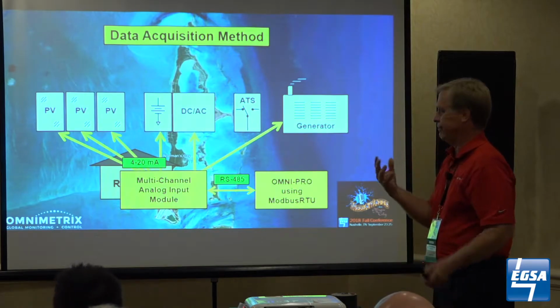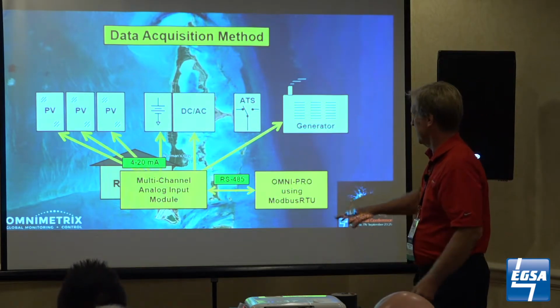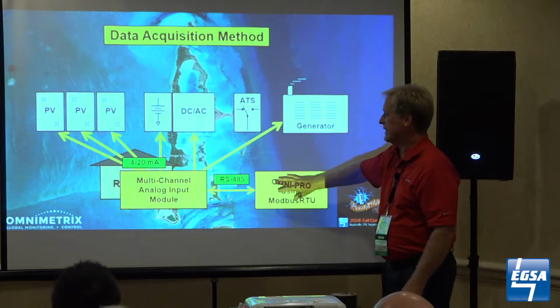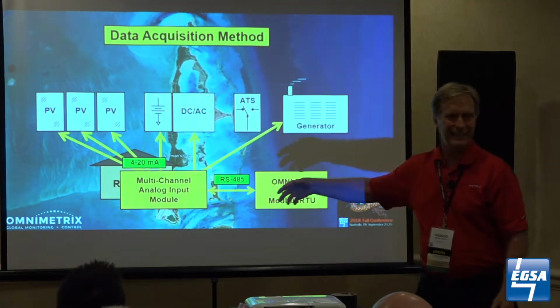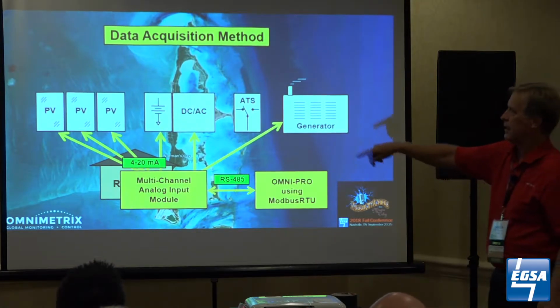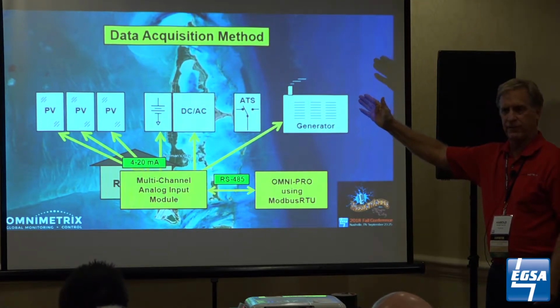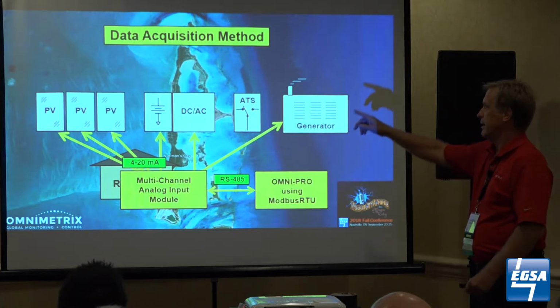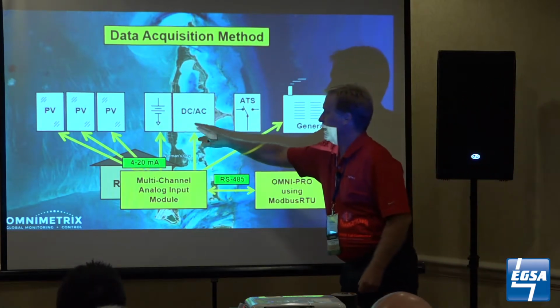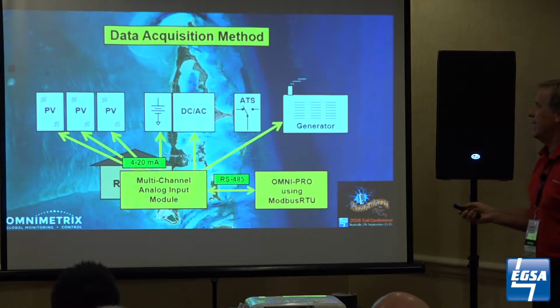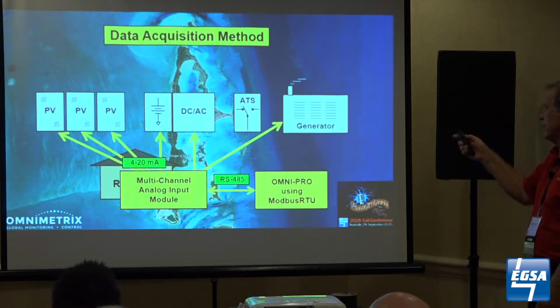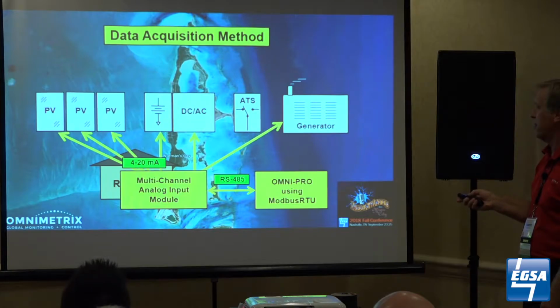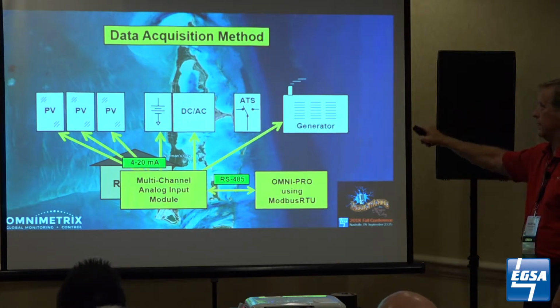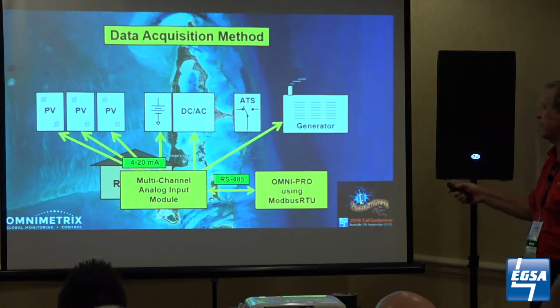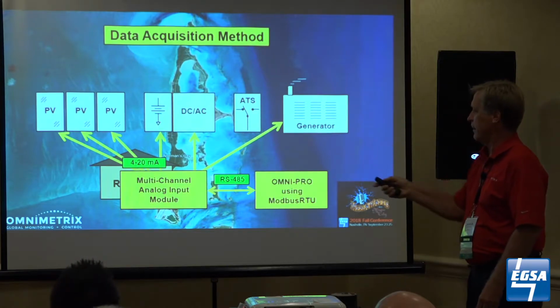From our system's requirements, the little black box you saw is this guy, and it's talking to an analog input module that allows us to pick up voltages from each of the photovoltaic banks, the battery itself, and the AC output of the inverter. Likewise, the output of the generator and its fuel, and of course battery. In fact, the system is powered by the genset battery.